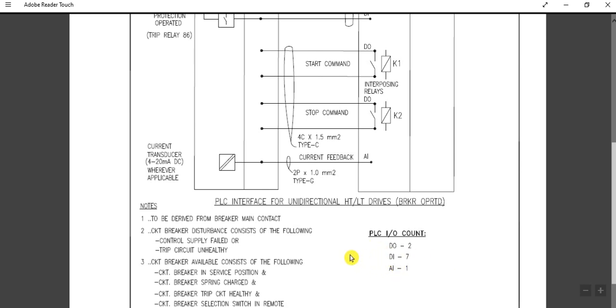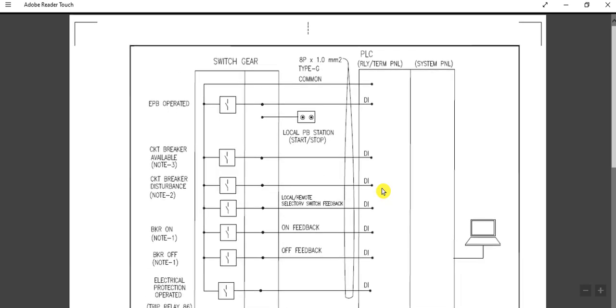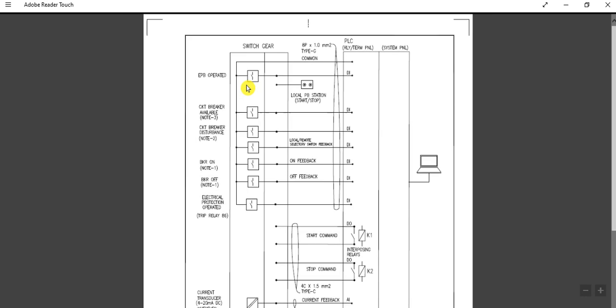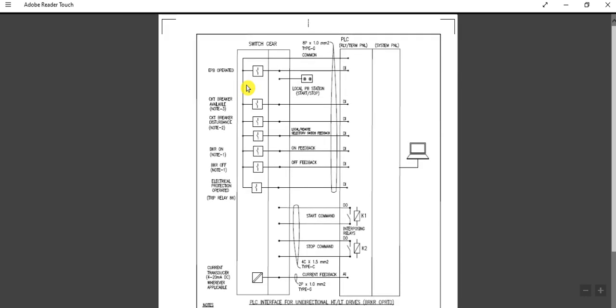Circuit breaker disturbance means control circuit fail or trip circuit unhealthy — this DI will be communicated to the PLC or DCS cabinet. Circuit breaker available consists of: circuit breaker in service position, breaker spring charged, breaker trip circuit healthy, and breaker selection in remote, not in local. This was the instrumentation point of the PLC or DCS interfacing scheme for a unidirectional HT/LT drive which is circuit breaker operated.